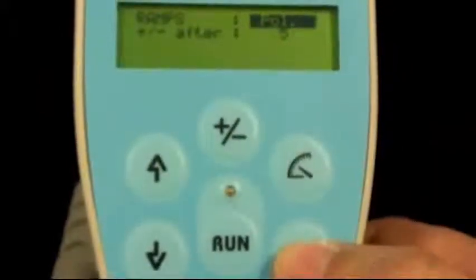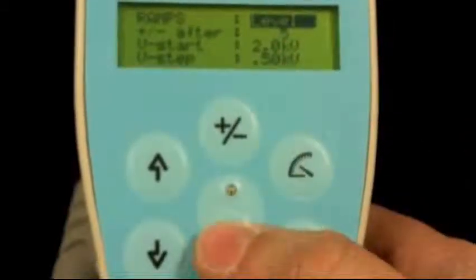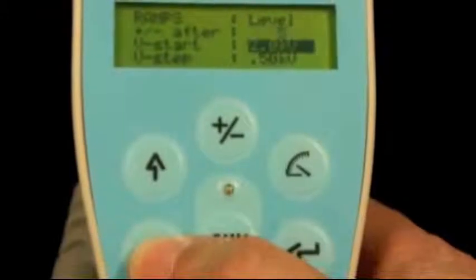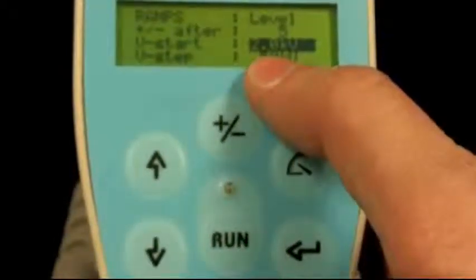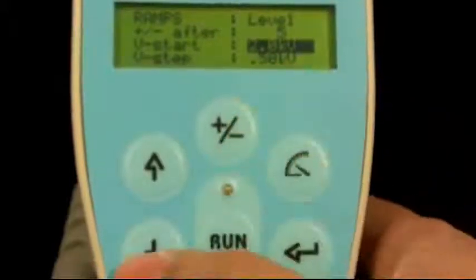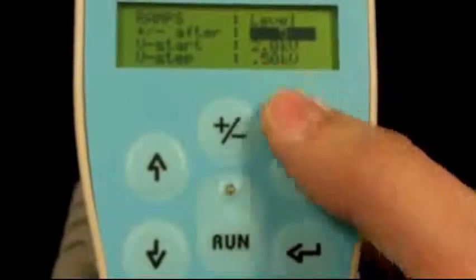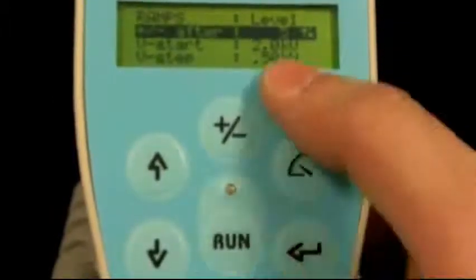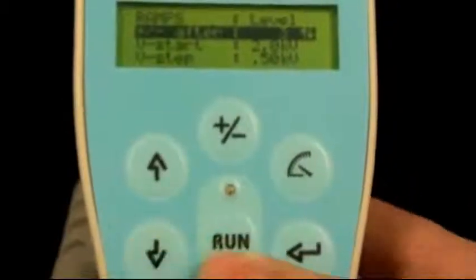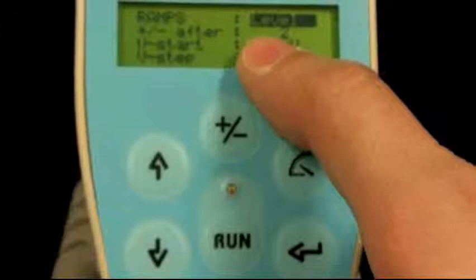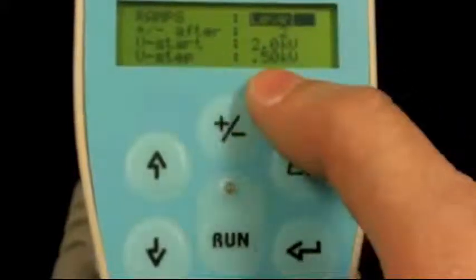The other ramp function available, instead of polarity, if you go back, hit enter again, you have levels. Scroll down and you can select, you can start at a certain level and after every pulse you can increase to a certain level. Hit enter, you can scroll down the number of pulses. So in this example, you would start at 2 kV and after every 2 pulses you would increase by 0.5 kV.